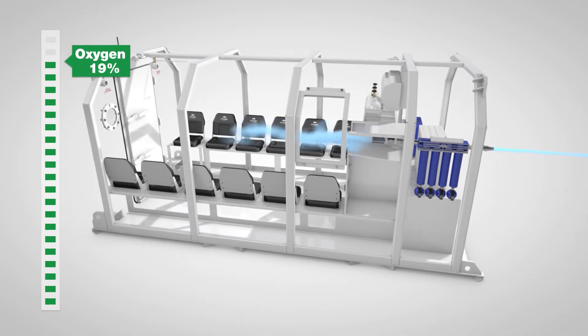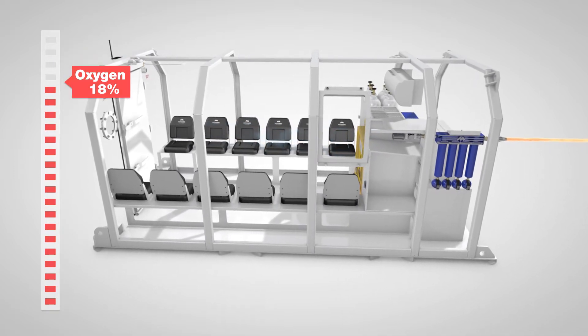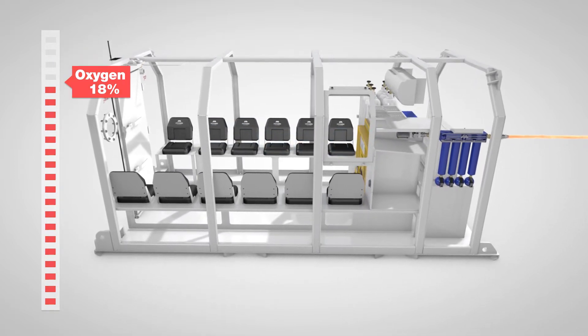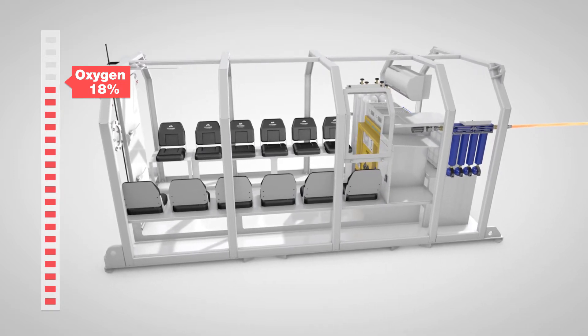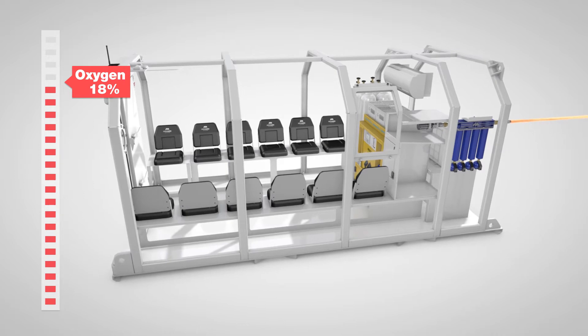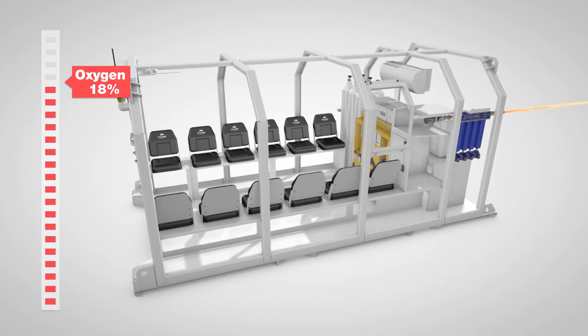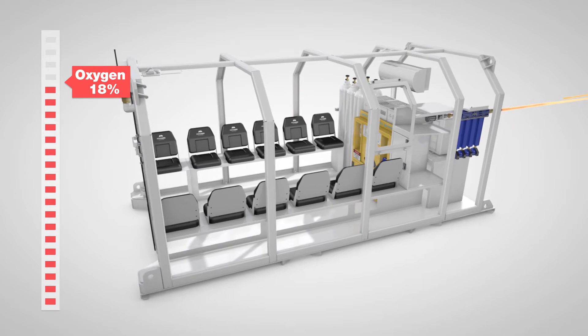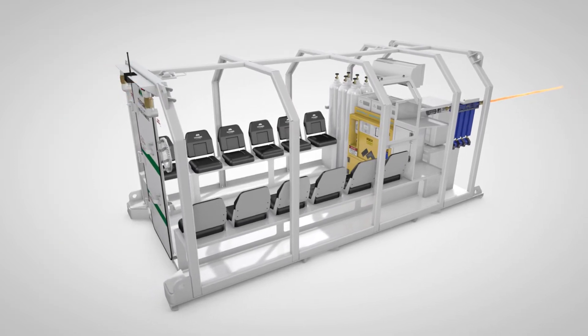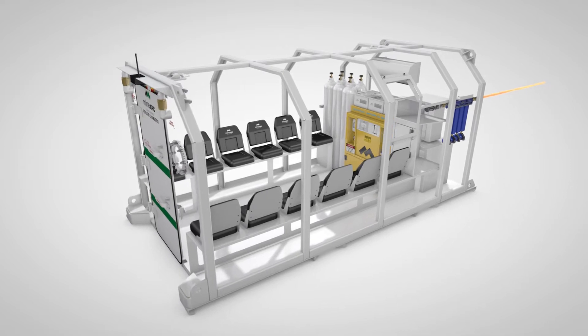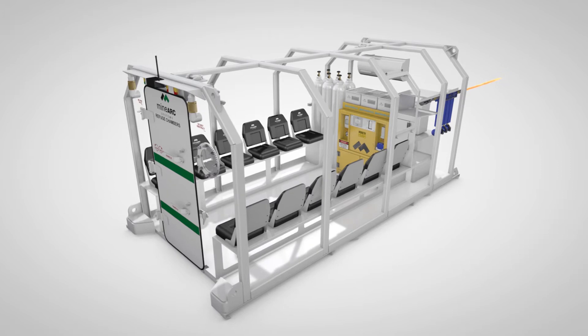The gas toxicity monitor activates a solenoid at the air intake which automatically shuts off compressed air if oxygen levels in the airline fall below 19%, signifying an offset caused by an increase in harmful gases entering the airline. Once activated, the CAMS auto shutoff solenoid will remain closed for the remainder of the entrapment, ensuring no toxins enter the chamber.